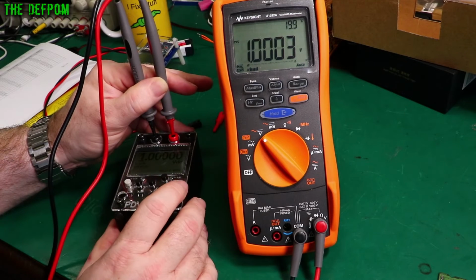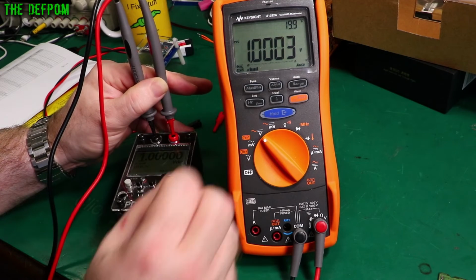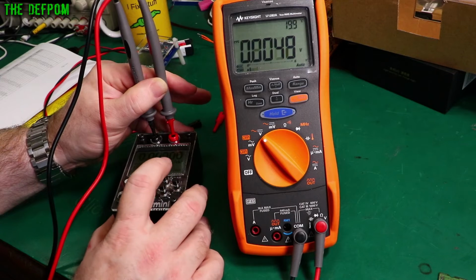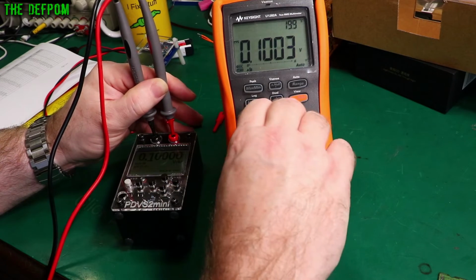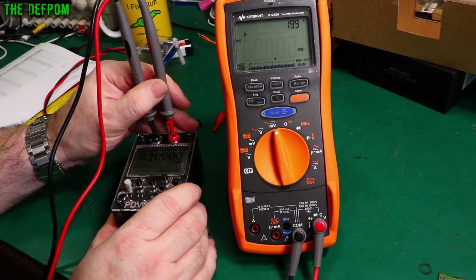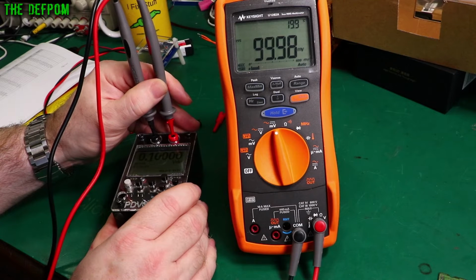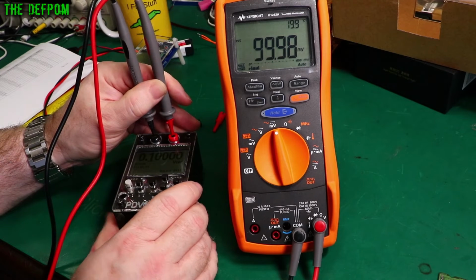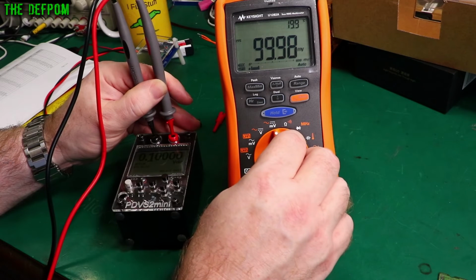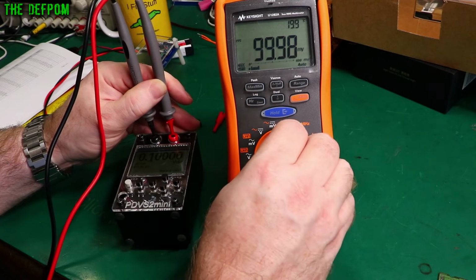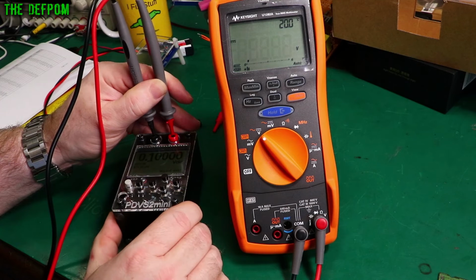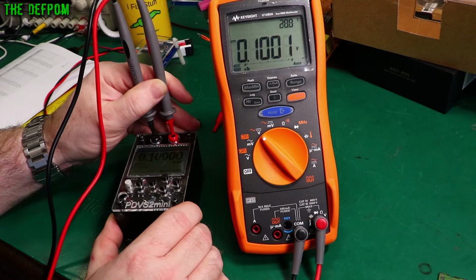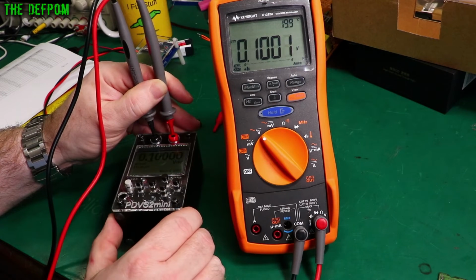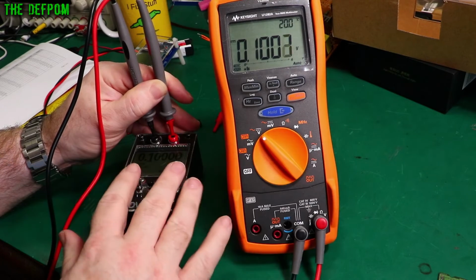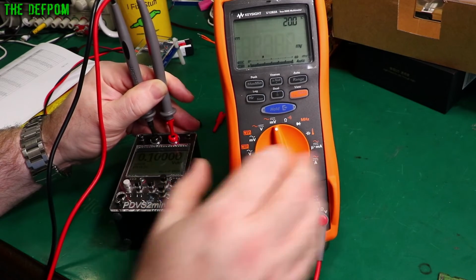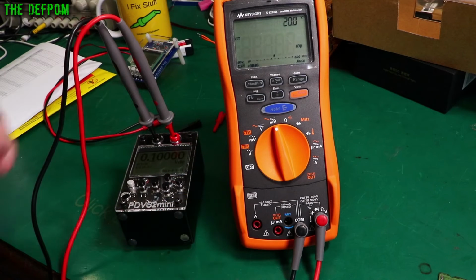This is a 60,000 count meter, by the way, as well. So 1 volt, 300 microvolts out. I don't know. Is it better? Okay. Let's try 100 millivolts. Let's go to DC millivolts. There we go. So in this mode it's reading 2 counts down, so that's like 20 microvolts down, but here it's reading 100 microvolts up. So I think it is a calibration thing on here. I don't think it's this. Pretty confident of that. So it's interesting that the actual specs said it was better than that.